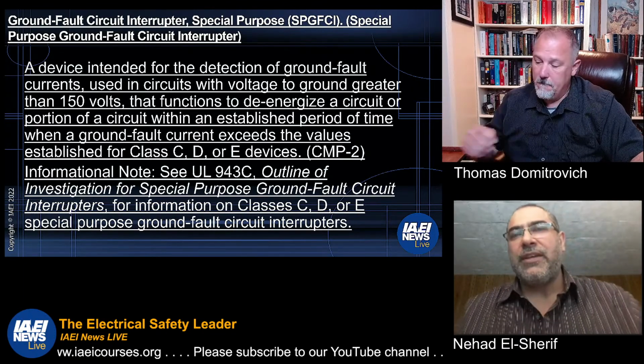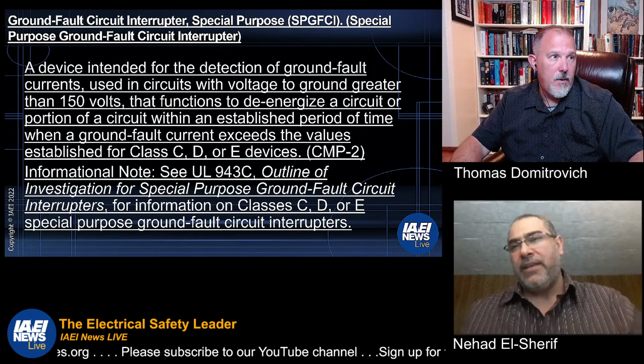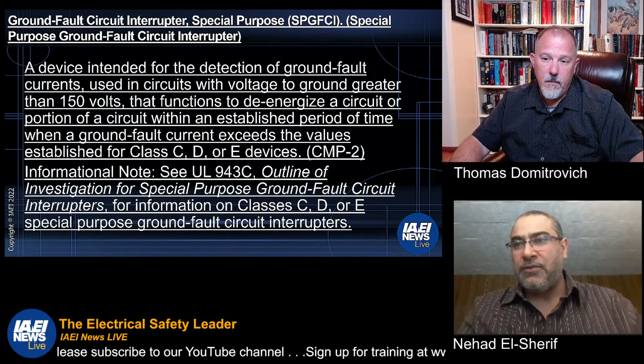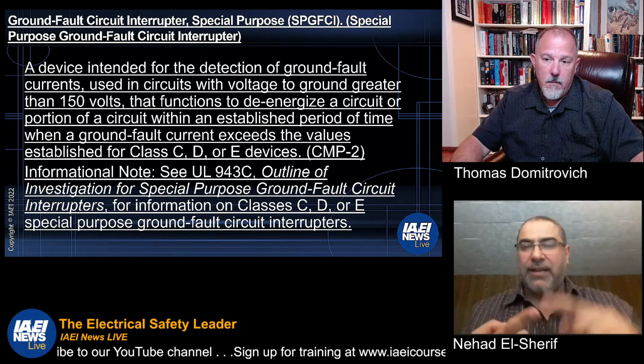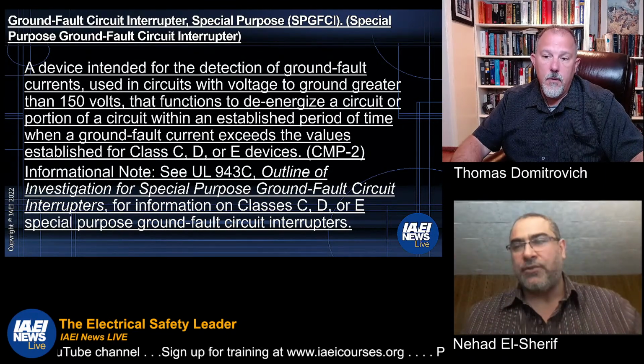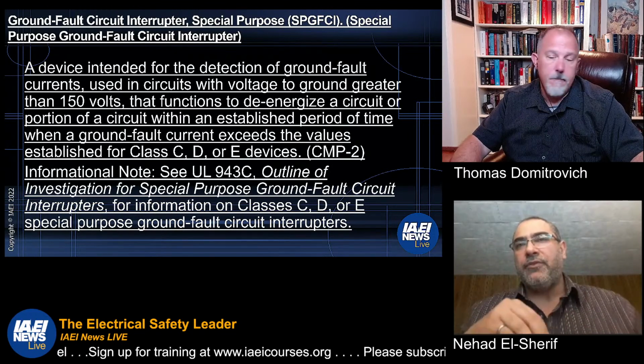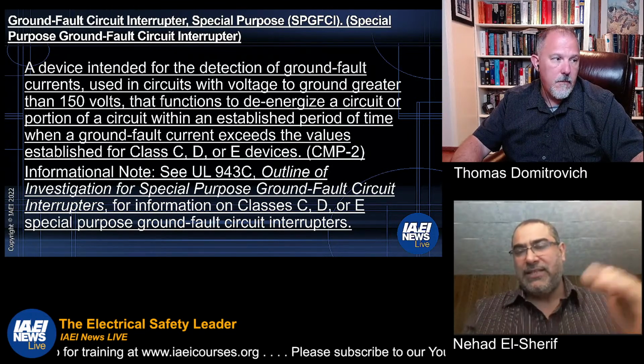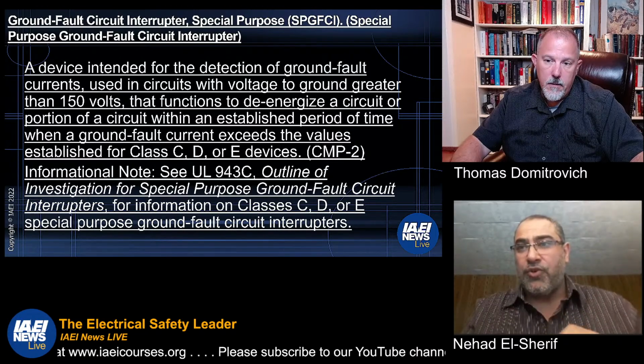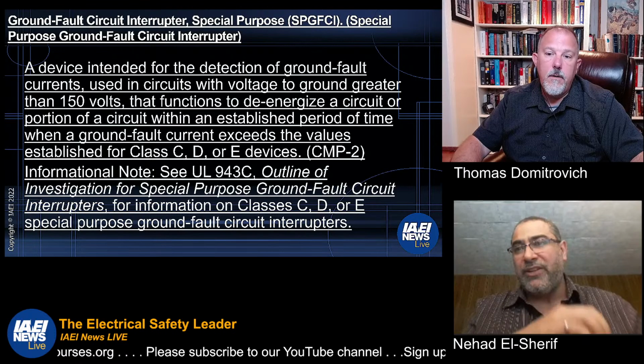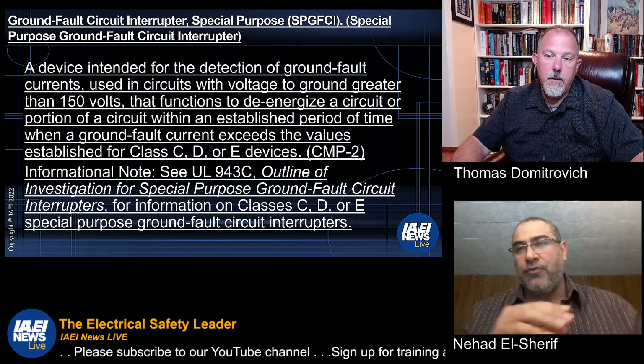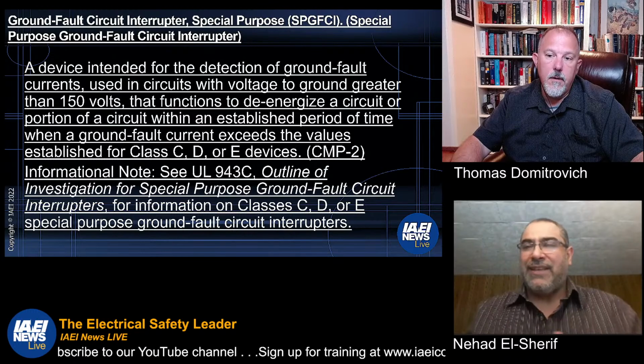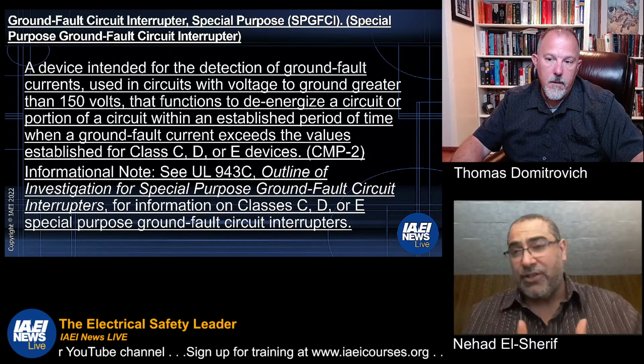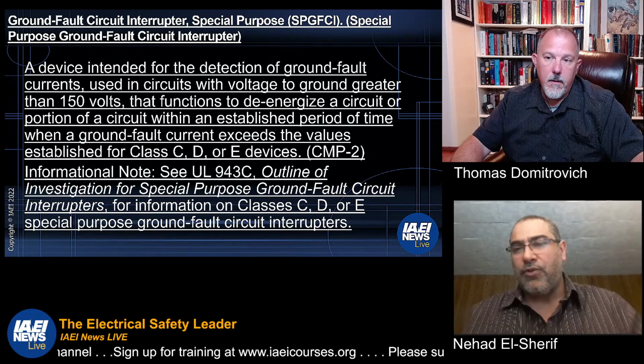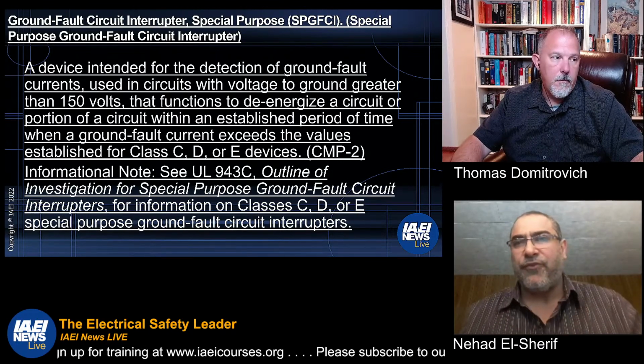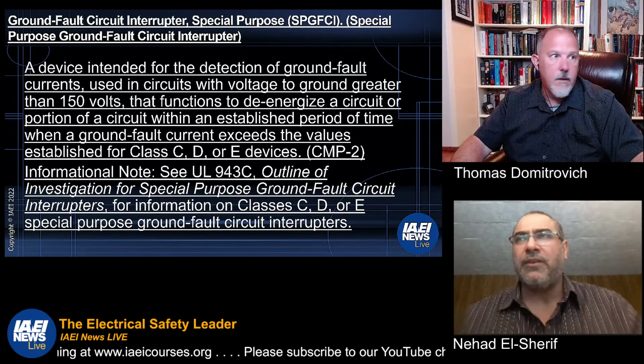I believe it's a non-Class A, because in Canada, UL 943 is a harmonized standard. So Class A is the same definition in Canada, US, and Mexico. It's like a North American standard. This was harmonized. UL 943C, Class A, C, D, and E, is only a US standard. So those classes are only defined in the US. Canada and Mexico are not using the same standard, but in Canada, before the harmonization of Class A, there was an old standard, which I don't remember the number of, but I can get it for whoever is interested. It's M91-something. I have it somewhere.